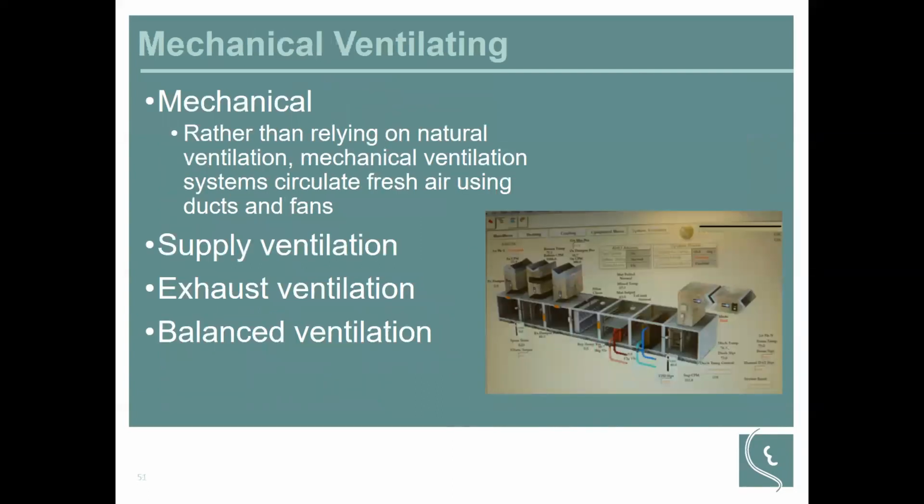A lot of us are familiar with mechanical systems. We use that rather than relying on natural ventilation. They have gotten to be some pretty complex systems. When we talk about mechanical ventilation, we can have supply ventilation, exhaust ventilation, and balanced ventilation. We try to have balanced ventilation all the time because we don't want to have a high interior pressure or a low interior pressure, because that's going to cause air to leak into our building assemblies or out of our building assemblies. So we try to balance the exhaust with the supply, which isn't always the case.